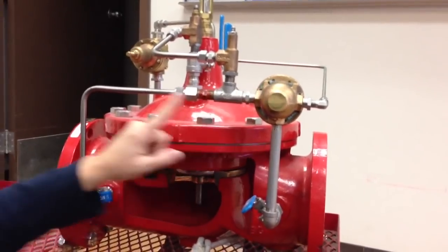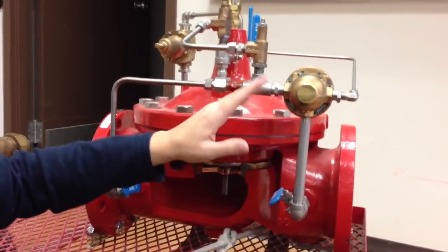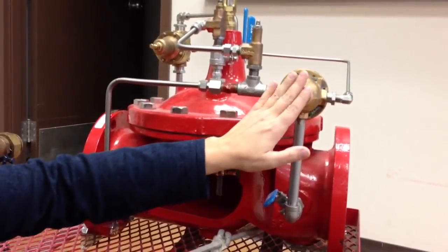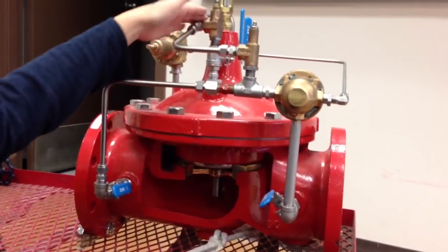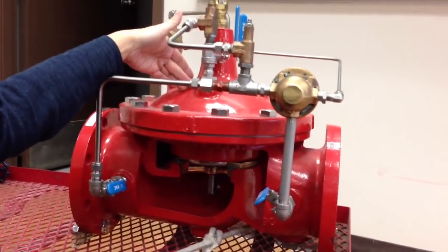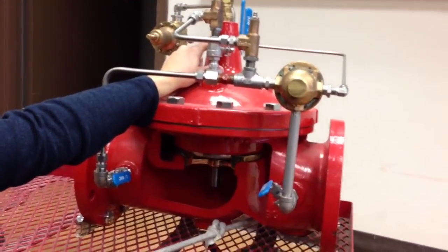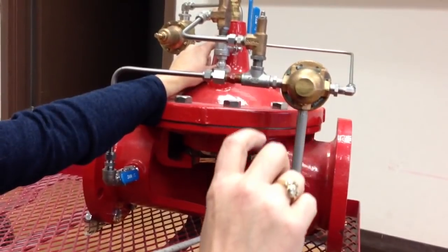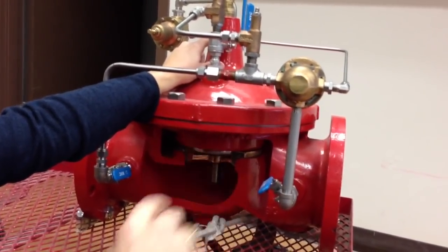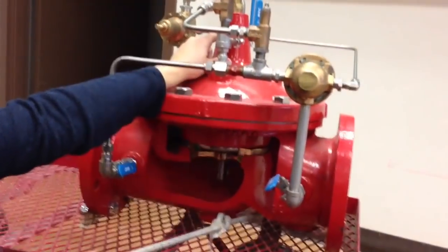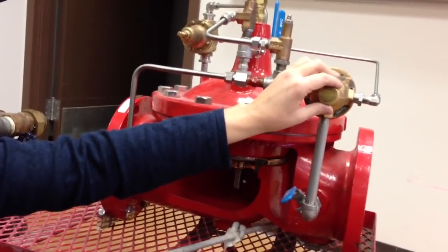When it closes, that 0.1 liters per minute is then forced, or a fraction of it, since it generally doesn't close all the way. More of it will be forced onto the top of the valve, which pushes the water in here, which forces this stem to travel down, which will start to close the valve. Now this process is very minute. We're not talking open, close. So this valve is going to be partially open almost all the time.